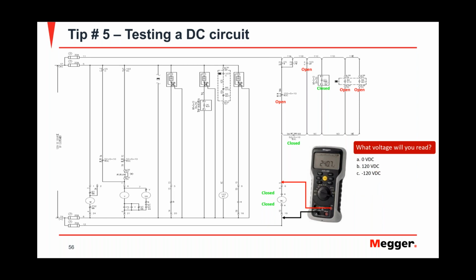I think I gave you the answer already. Let's say now you're testing your relay, and the moment the relay trips the breaker, this contact closes. The moment this contact closes, and let's say you left your meter from last example, and you want to see the voltage at your trip coil, what voltage would you expect to see?